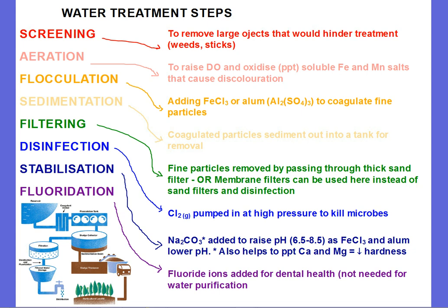You've got the sedimentation step next, which is where coagulated particles sediment out into a tank for removal. You've got filtering, where fine particles are removed by a filter, usually a sand filter, or at this stage you could also use membrane filtration, which we'll look at in just a minute. Then you've got disinfection. You add chlorine gas, which is pumped in at high pressure to kill microbes or microorganisms.